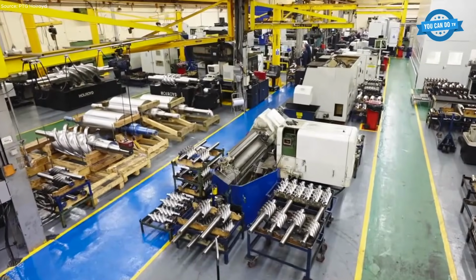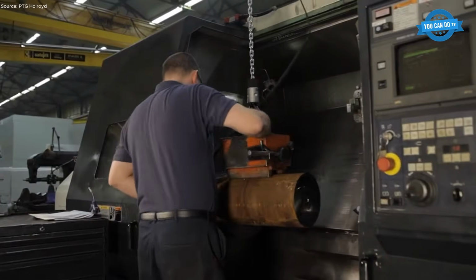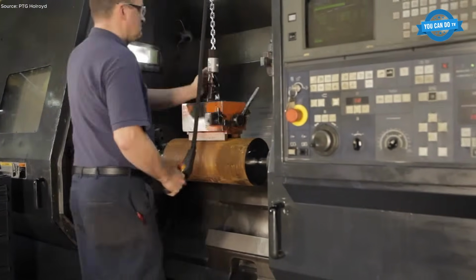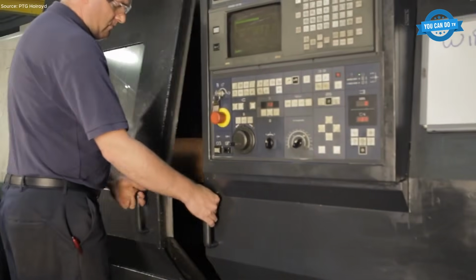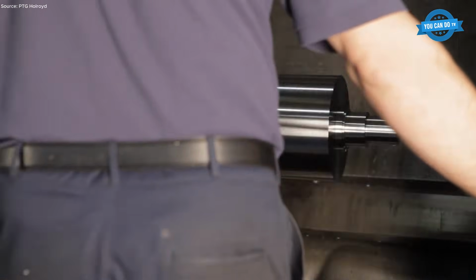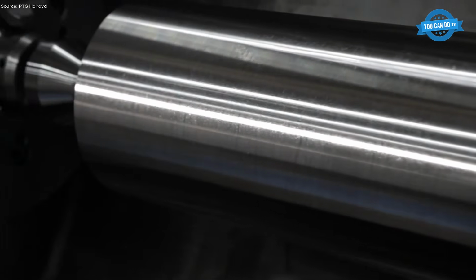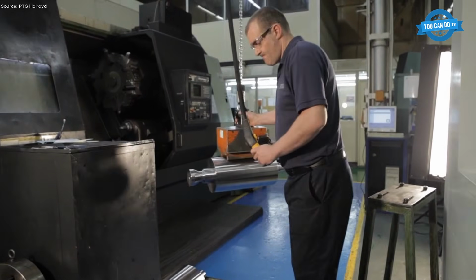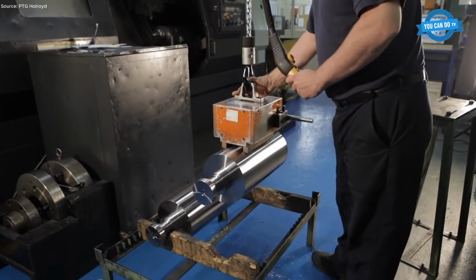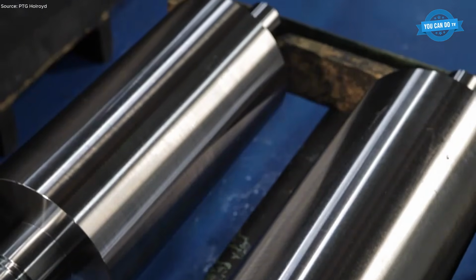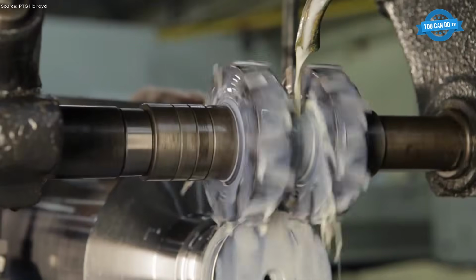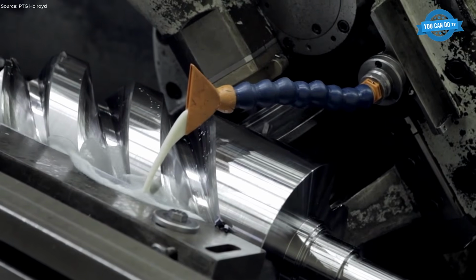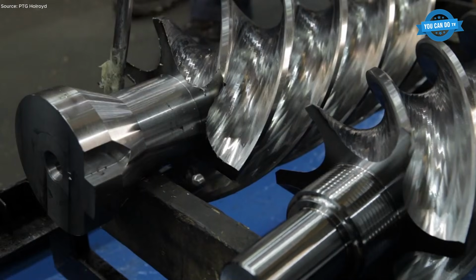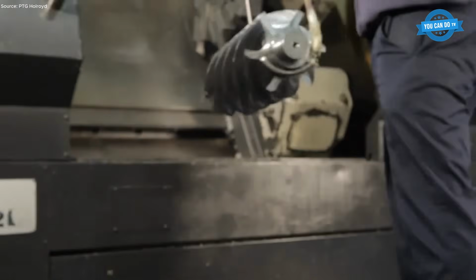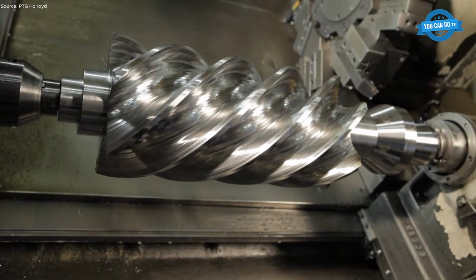At Holroyd, screw and rotor manufacturing is a highly controlled precision process where geometry, surface quality, and micron-level accuracy define final performance. Production begins with carefully selected steel billets, which are pre-machined to establish reference diameters and centers before entering the rotor manufacturing line. The core of the process takes place on advanced CNC rotor milling and grinding machines, purpose-built to generate complex helical profiles.